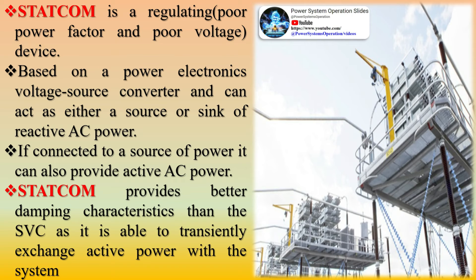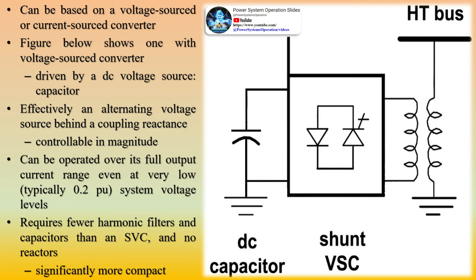Advantages of STATCOM: the reactive components used in the STATCOM are much smaller than those in the SVC. The characteristics of STATCOM are superior. The output current of STATCOM can be controlled up to the rated maximum capacitive or inductive range. Reduction of the capacity of semiconductor power converter and capacitor bank to one half of those for conventional SVC. Better transient response of the order of quarter cycle. Reduction of harmonic filter capacity, reduction of size of high-value air-core reactor, and reduction of equipment volume and footprint.